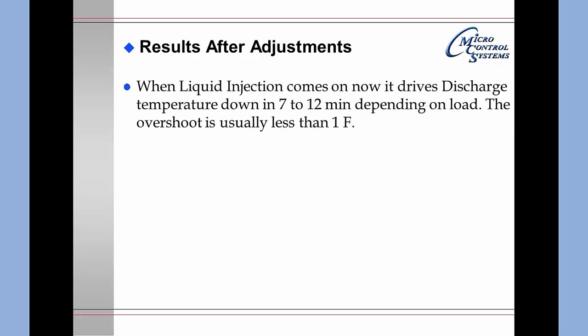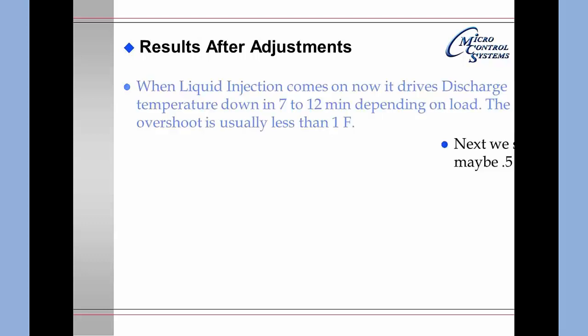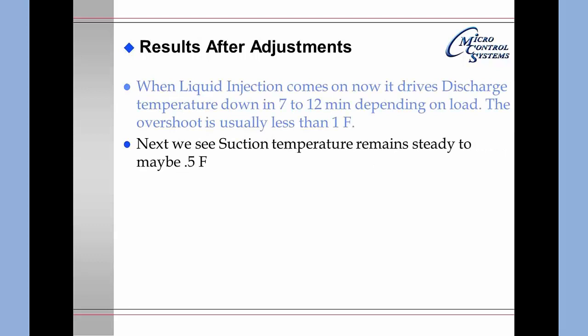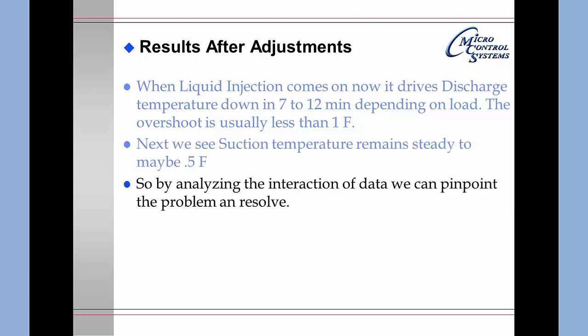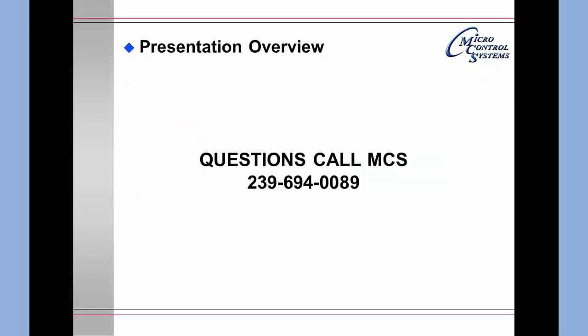When the liquid injection comes on it now drives the temperature down in 7 to 12 minutes depending on the load, and the overshoot is usually less than 1 degree. The suction temperature remains steady to within about a half a degree. By analyzing the interaction of data we can pinpoint the problem and resolve it. If you have any questions, call MCS at 239-694-0089.